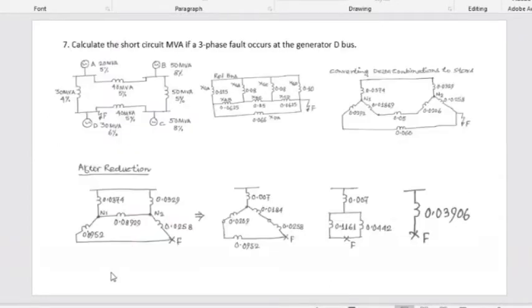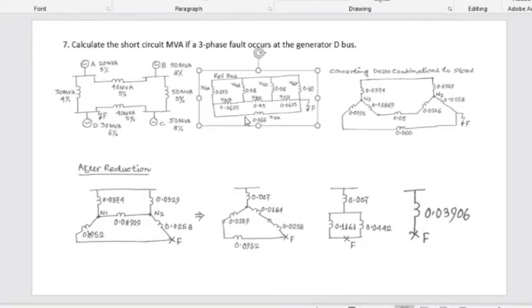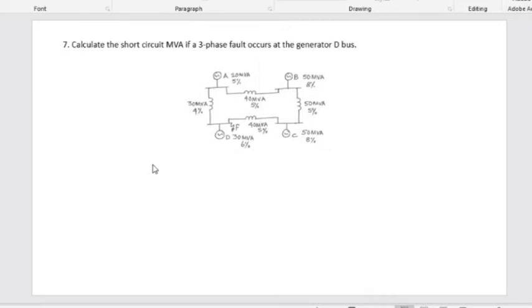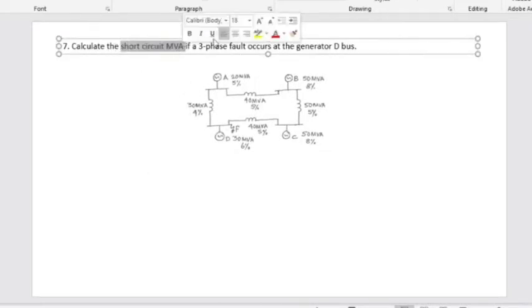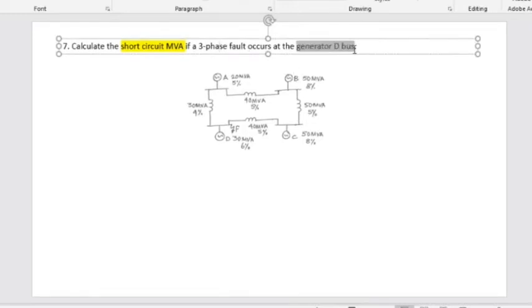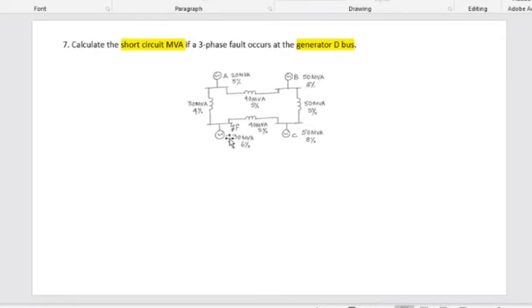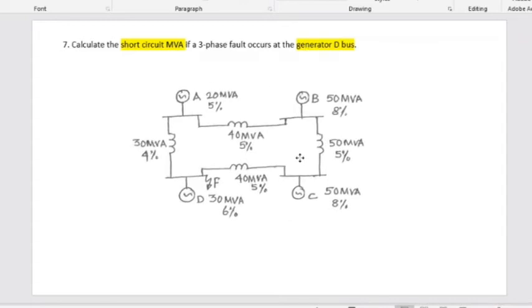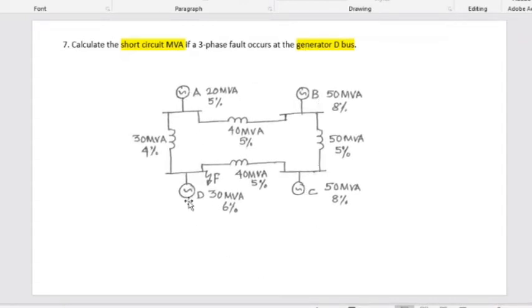The next example is a ring main system. We have to calculate the short circuit MVA when a three-phase fault occurs at the generator D bus bar — the fault point is shown there. We have generators A, B, C, and D. Generator A is rated at 20 MVA with 5% reactance. Generator B is rated at 50 MVA with 8% reactance. Generator C is also 50 MVA with 8% reactance. Generator D is 30 MVA with 6% reactance.